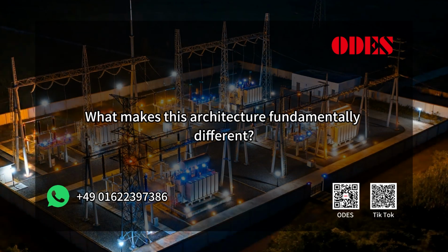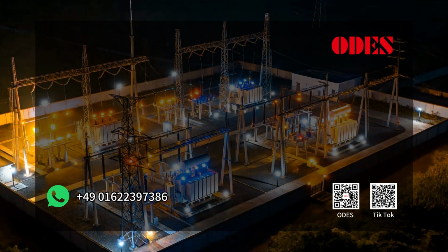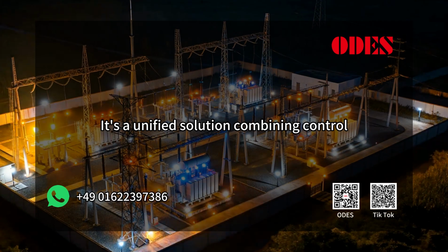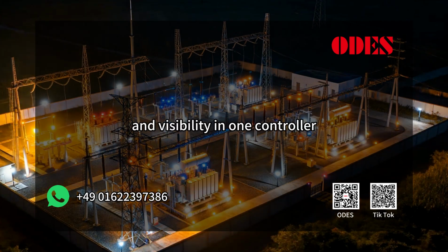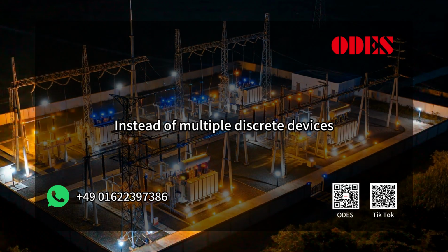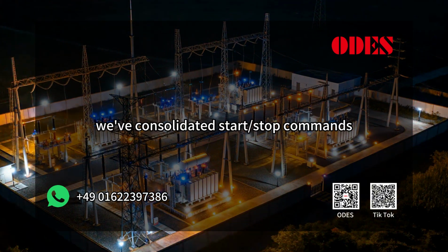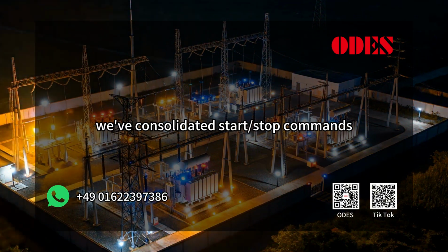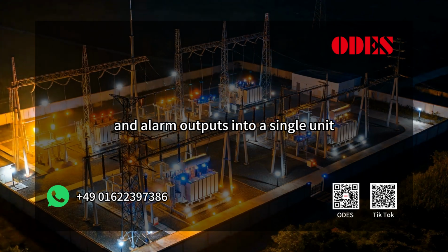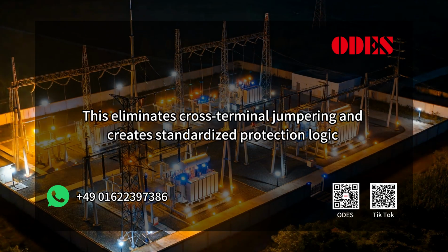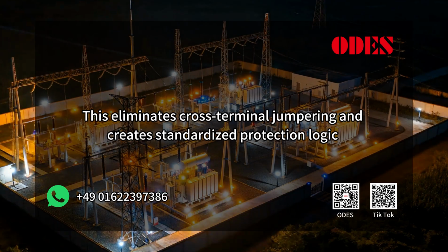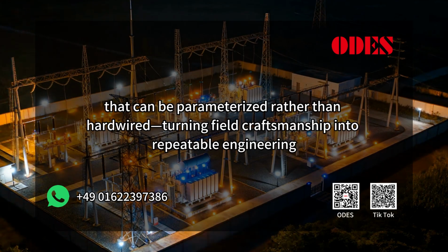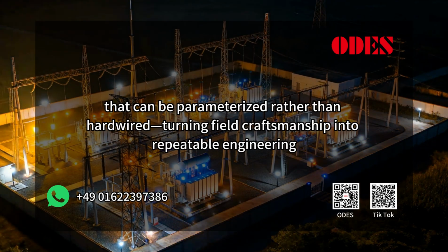What makes this architecture fundamentally different? It's a unified solution combining control, protection, and visibility in one controller. Instead of multiple discrete devices, we've consolidated start-stop commands, fault detection, and alarm outputs into a single unit. This eliminates cross-terminal jumpering and creates standardized protection logic that can be parameterized rather than hardwired, turning field craftsmanship into repeatable engineering.